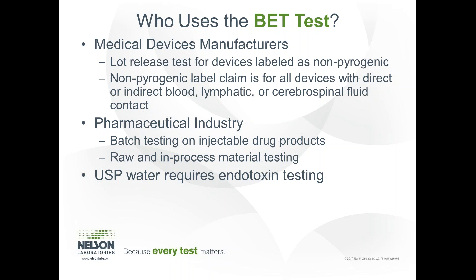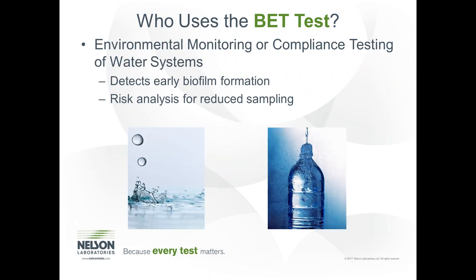BET testing is used for medical device manufacturers. It is typically done as a lot release test for any device that is in contact with the circulatory system, the lymphatic system, or cerebral spinal fluid. This test can be used to support a non-pyrogenic label claim. The pharmaceutical industry also uses endotoxin testing for injectable drug products and raw materials. We can also use the BET test as an environmental monitor for water systems, as the BET assay is one of the most sensitive tests in the world and can detect the early formation of biofilms that could contaminate a water system.